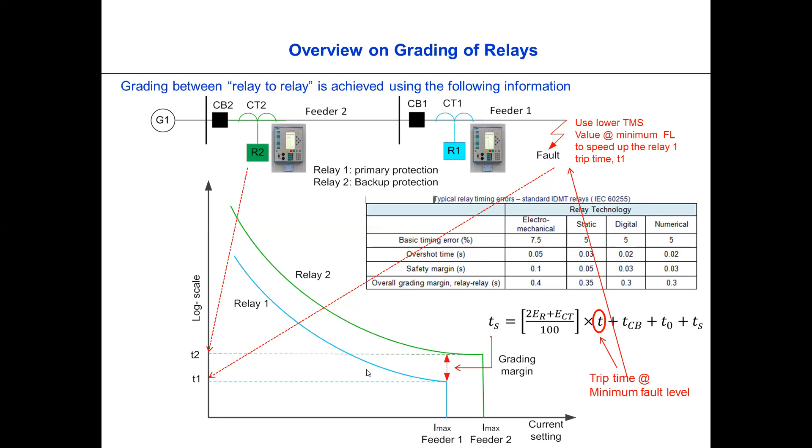And then the next step is we can then add this T1 with the grading margin. And then we can call it T2, so that this relay will trip the fault on here at time 2. So that T2 would be T1 plus the grading time. Then this is the trip time at time 2.